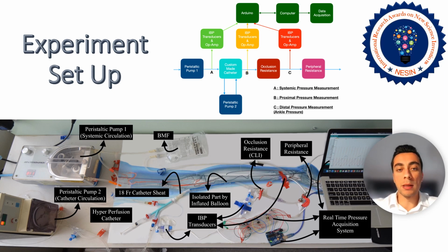A second extracorporeal peristaltic pump was connected to the custom-made catheter. Blood mimicking fluid was prepared to simulate the dynamic viscosity of blood. To measure the dynamic pressure, three invasive blood pressure transducers were used. The first transducer was placed at the output of the primary peristaltic pump, which represents systemic pressure. The second transducer was placed to measure assisted circulation pressure right below the inflated compliant balloon. The third transducer was placed distal to the simulated collateral circulation, which represents the ankle pressure. A custom-made electrical circuit design and a computer were used to do data acquisition.